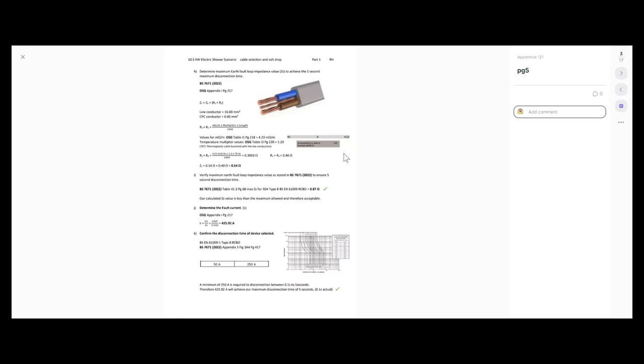Based on that value of ZS, I need to consider the actual fault current that's going to be generated. Going back into the on-site guide, Appendix I on page 217 — it gives us the formula using Ohm's law. Fault current is U0 divided by ZS. Our nominal voltage of 230 volts divided by ZS of 0.54 ohms gives a fault current of 425.92 amps. That's a lot of current going to be generated — a lot of juice.